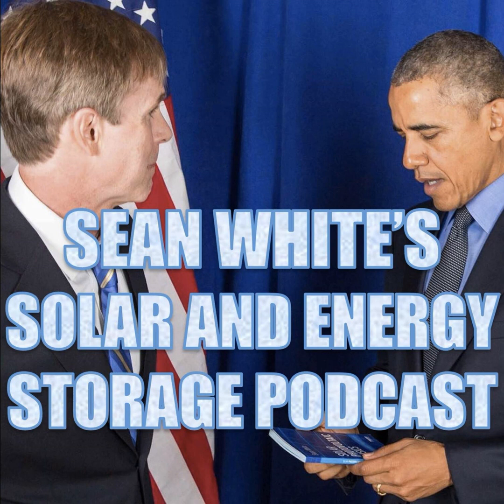We've had it in commercial for decades. Energy management systems have been common, but the concept is working its way into residential. Stuff that you would have on your iPhone or whatever, that you'd be able to turn things on and off in your house. And of course, you'd want to have that in a backup power system so you could program what breakers to shut off. So the whole idea here is that in a microgrid, you could basically say, when you go into microgrid mode, instead of having to rewire your whole house, I am going to lock out my electric dryer. I'm going to lock out my electric water heater. I'm going to lock out my air conditioner so that those things don't try to run off of my inverter, because my inverter is not big enough to run all those things and my refrigerator.